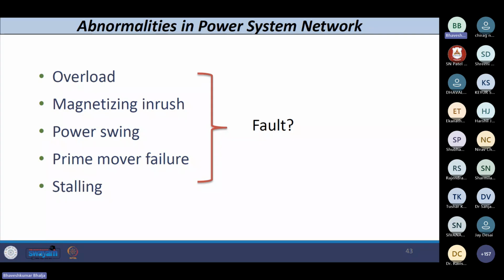Because when there is overload, when equipment or a conductor draws current above its rated value, the increase in magnitude is very slow. It is not rapid. Whereas in the case of a fault, the increase in magnitude is a very rapid phenomenon, right? di/dt is very high in the fault case. Sometimes you have inrush also, magnetizing inrush.